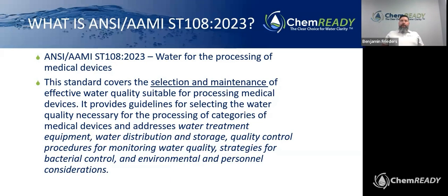This can be anywhere from critical, semi-critical, non-critical medical devices, and all the sterilization required to perform surgery or medical procedures. It encompasses the guidelines for water treatment equipment, water distribution and storage, the quality control procedures for monitoring that water quality, strategies for bacteria control, and environmental and personnel considerations.